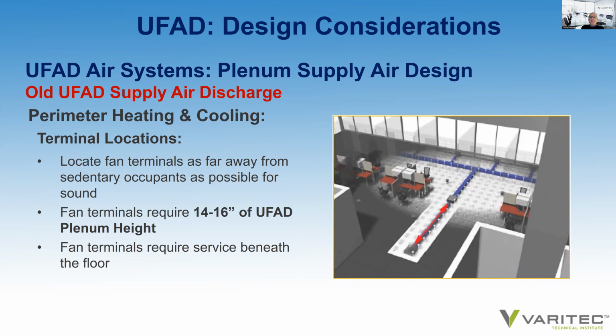How do we condition the perimeter zone of a UFAD system? The traditional way of doing it is to line the perimeter floor with a linear diffuser and supply air from a fan-powered terminal unit. The problem is those fan-powered terminal units are deep. They have a fan in them, and they come initially with filters as well. And those fan assemblies require plenum heights of 14 to 16 inches so they'll fit under the floor. And that's why plenums were designed to that point.